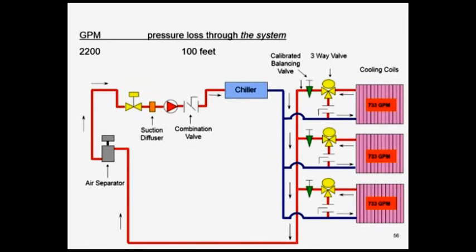Remember that function of system curves. Let's go back to that same little formula again. If I double the flow to a given system, then the friction loss is going to go up 4 times. In other words, if I double the flow in this system from 2,200 GPM to 4,400 GPM, the pressure drop is going to go from 100 feet to 400 feet. It's going to go up 4 times because of that square function. And now I'm beginning to calculate and produce a system curve. I can take that same logic and go the other way. Take the 2,200 GPM and cut it in half to 1,100 GPM, and my system pressure drop would be 25 feet. If I cut the 1,100 GPM in half again, 550 GPM becomes 6 feet. So you're beginning to see how the system will perform on its system curve based on the flow rate through that system. And that becomes your system curve.